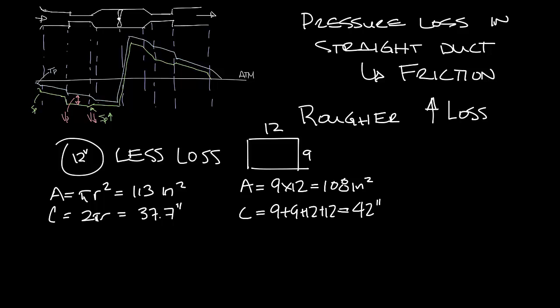Now if you look at the rectangular ductwork, the area is 9 times 12 which is 108 square inches and the perimeter is 9 plus 9 plus 12 plus 12 is 42 inches. So you can see that there's a little less area in the 9 by 12 duct but it has more surface area to interact with the air. So the closer to round or even square you can get, the lower the loss.